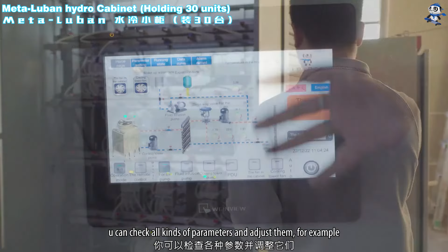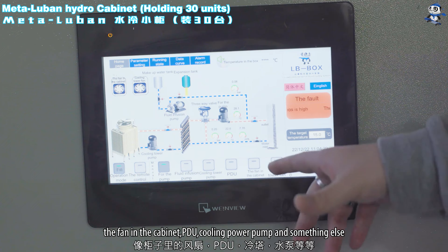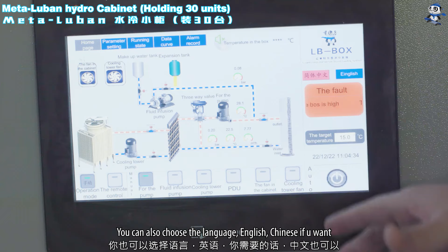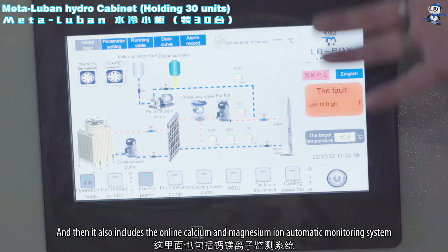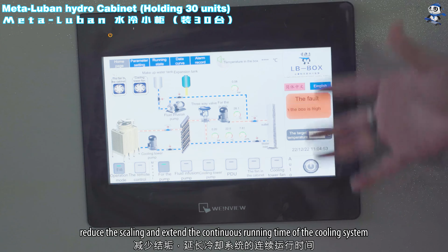Okay, now let's check the remote controlling screen. You can check all kinds of parameters and adjust them. For example, the fan in the cabinet, PDU, the tower pump, and something else. You can also choose the language, English or Chinese if you want. And it also includes the online calcium and magnesium ion monitoring system to achieve the automatic fixed discharge of old water from the cooling tower, reduce the concentration of calcium and magnesium ions, reduce the scaling, and extend the continuous running time of this cooling system.